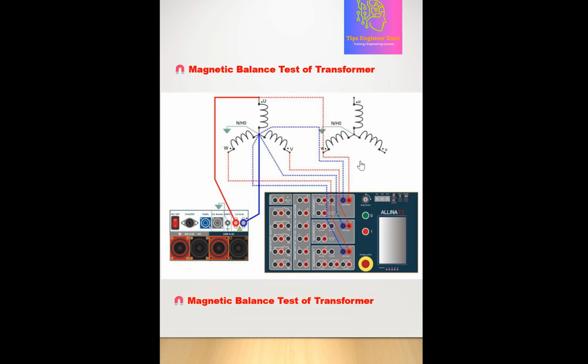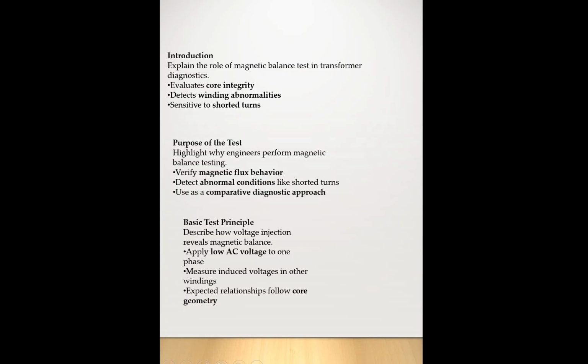Okay, so this is the magnetic balance test, and this is the instrument. Okay, so the magnetic balance test is performed on a transformer. The role of the magnetic balance test in a transformer is to evaluate core integrity, detect winding abnormalities, and check the sensitivity to short turns. Okay, and this is very important for core integrity.